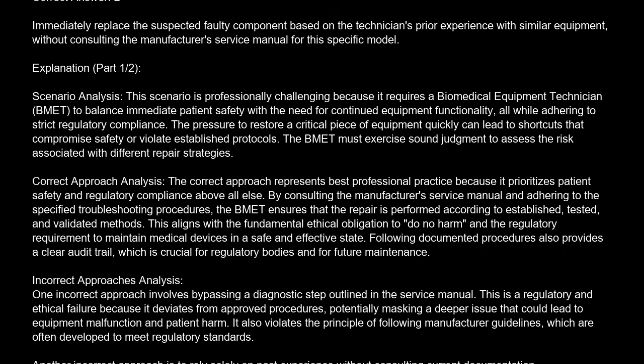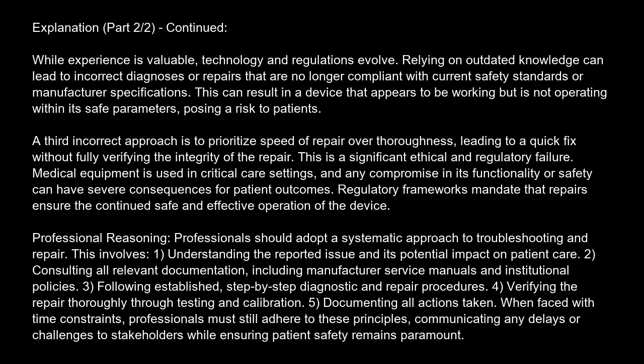Another incorrect approach is to rely solely on past experience without consulting current documentation. While experience is valuable, technology and regulations evolve. Relying on outdated knowledge can lead to incorrect diagnoses or repairs that are no longer compliant with current safety standards or manufacturer specifications. This can result in a device that appears to be working, but is not operating within its safe parameters, posing a risk to patients. A third incorrect approach is to prioritize speed of repair over thoroughness, leading to a quick fix without fully verifying the integrity of the repair. This is a significant ethical and regulatory failure. Medical equipment is used in critical care settings, and any compromise in its functionality or safety can have severe consequences for patient outcomes. Regulatory frameworks mandate that repairs ensure the continued safe and effective operation of the device.